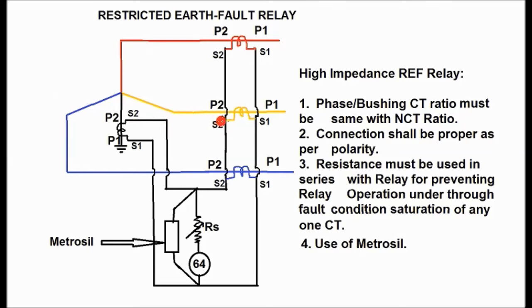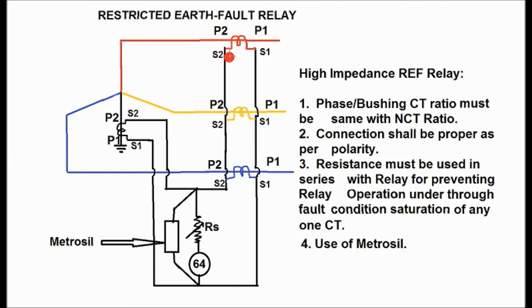Why is restricted earth fault protection used? Restricted means for a particularly defined zone. The neutral CT and the bushing CT form this restricted zone, and if an earth fault occurs within this zone, then only this relay will detect and send a trip signal to the circuit breaker.